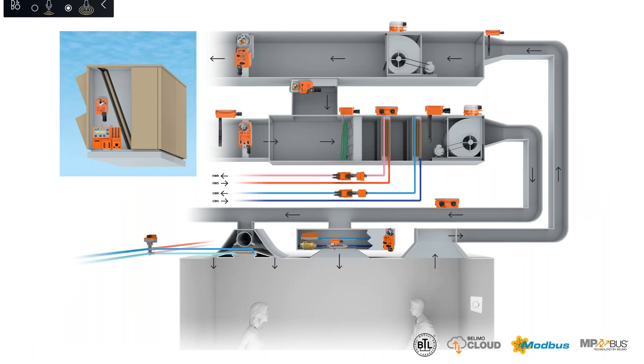Let's take a look at an example of an air handling unit. Actuators, sensors, and valves are the interface between the control system and the mechanical system — they're critical in ensuring reliable and efficient operation. Typically, 80% or more of the DDC outputs in an HVAC system go to the actuators. If they're not operating properly, then all other portions of the system will suffer.